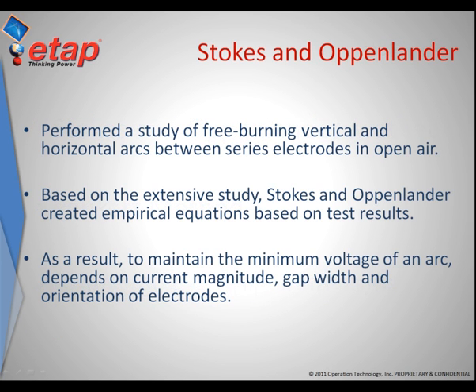The Stokes and Oppenlander method is an empirical method derived from free burning vertical and horizontal arc tests in a series electrode configuration for arcs in open air. The tests were extensive and compiled by Stokes and Oppenlander. Based on these tests, a set of empirical equations were created. As a result of these equations, we can use the gap between conductors to determine the actual magnitude of the arcing current.